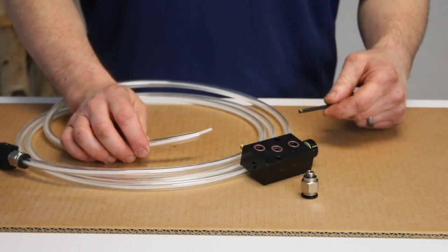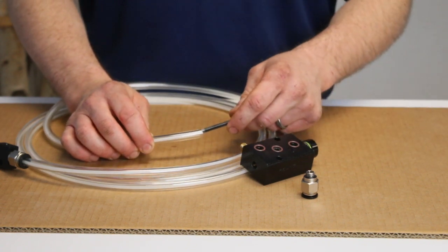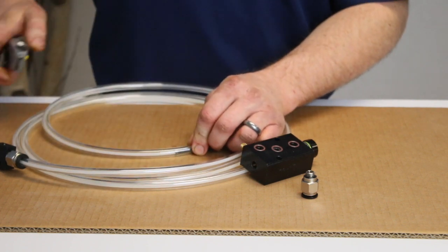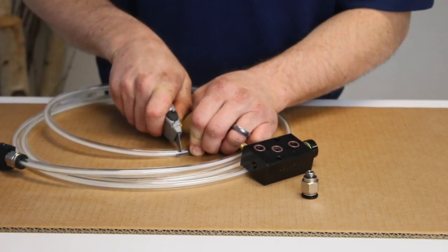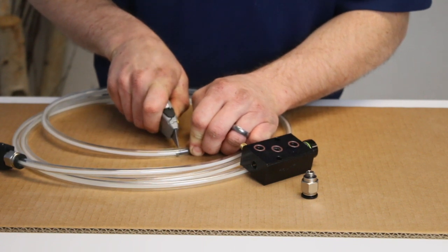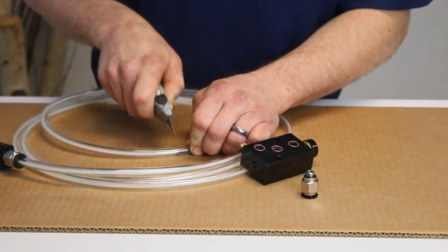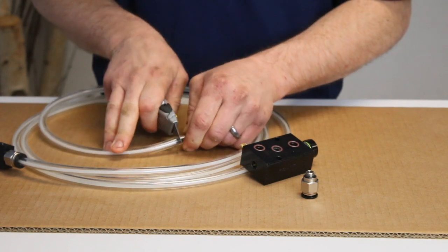Instead we recommend inserting a tool into the 3/8 tube and pushing the capillary back in, and then cutting right along where the tool was inserted. This ensures that you won't nick or damage the 1/8 inch capillary line at all.